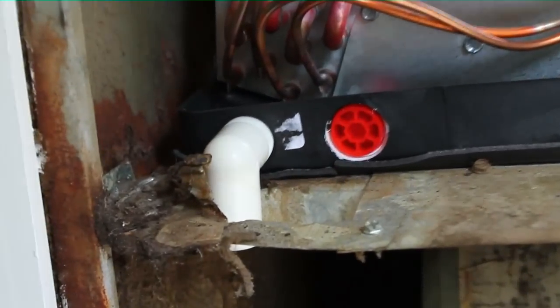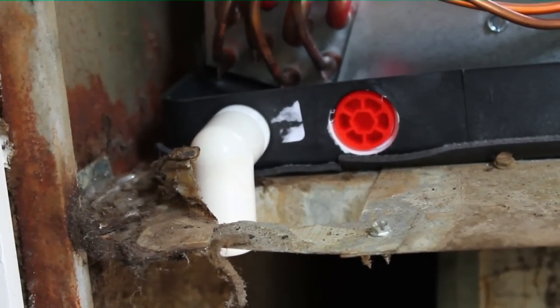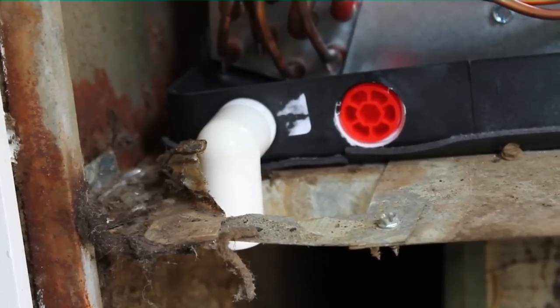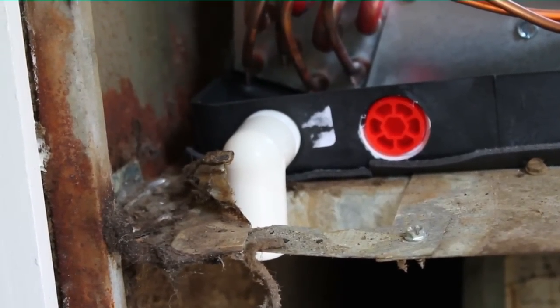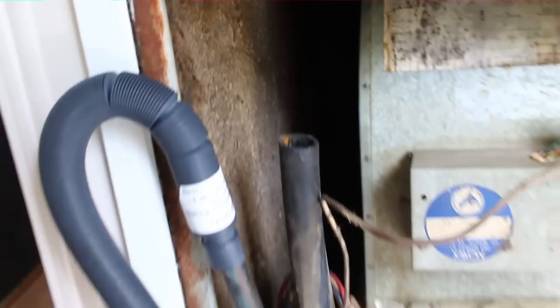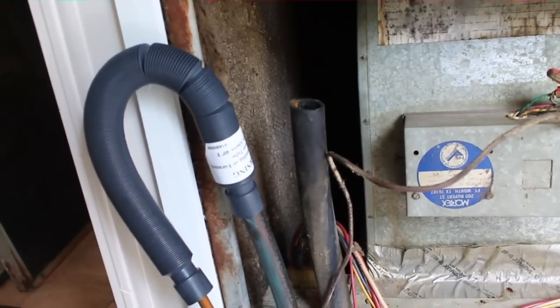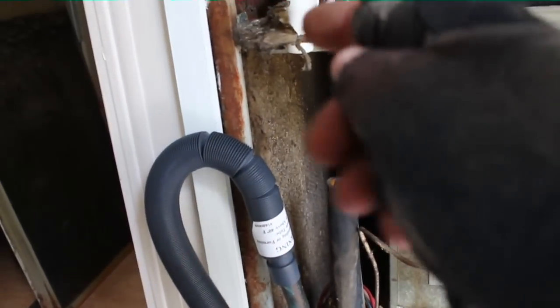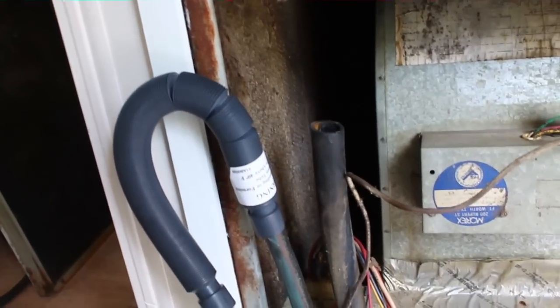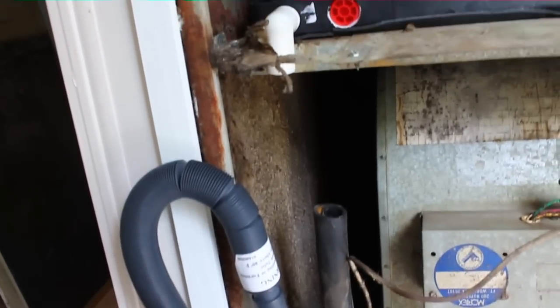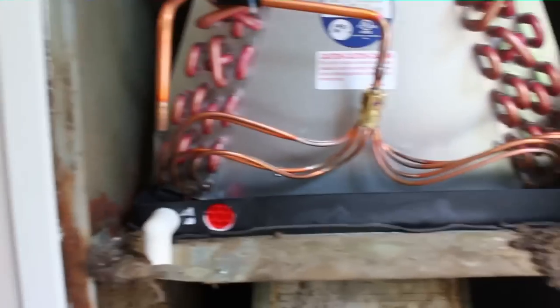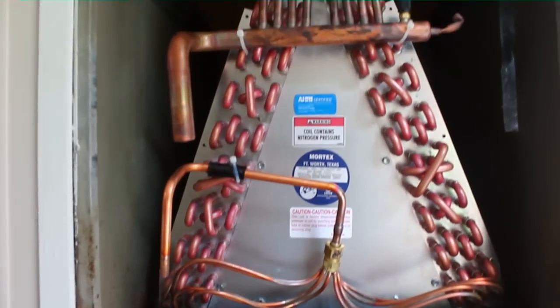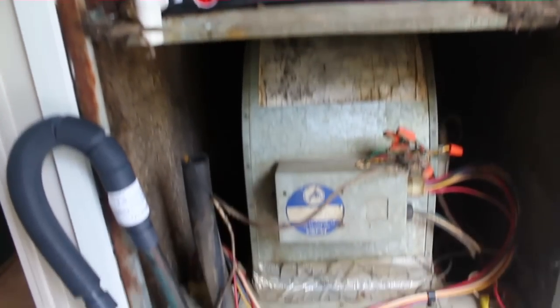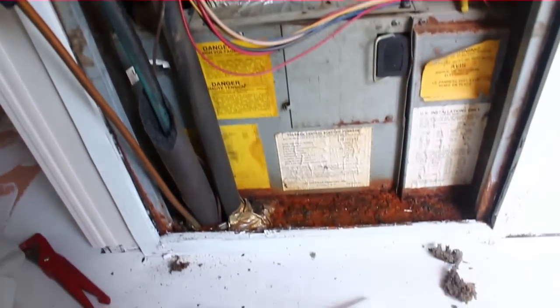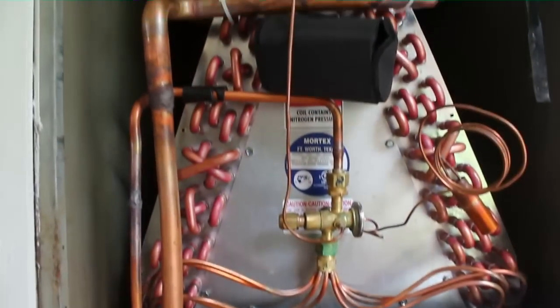Making sure to put our drain fitting in place, because once all our lines are tied in, it'll be real hard to screw that 90-degree drain fitting in place. This black tubing, we can actually pull it up. It'll go over the top of the drain fitting and be crimped in place with a little pipe clamp they send with you. So that looks like it'll work out just fine. I had to blow out that drain before we do that and blow out these lines, but that is no problem.